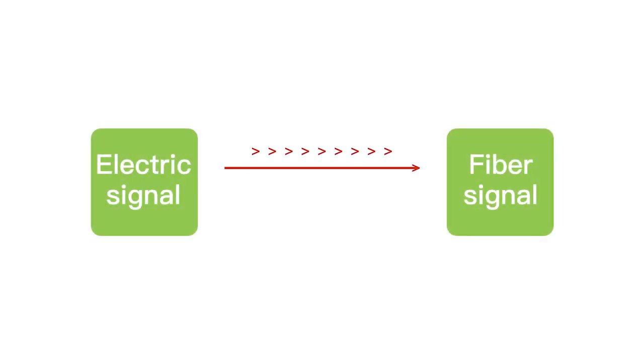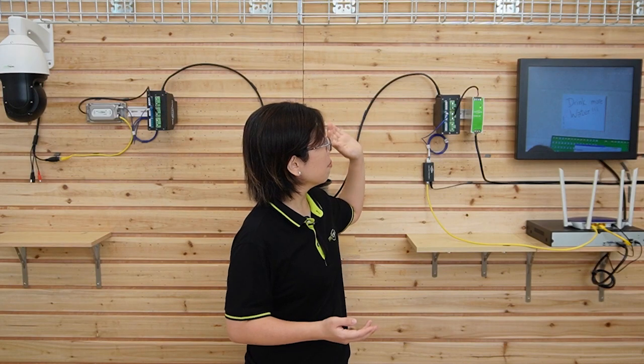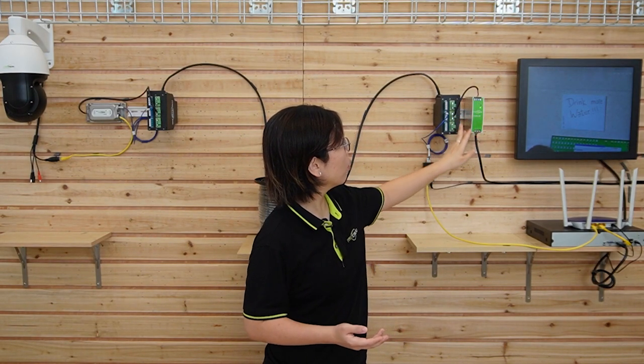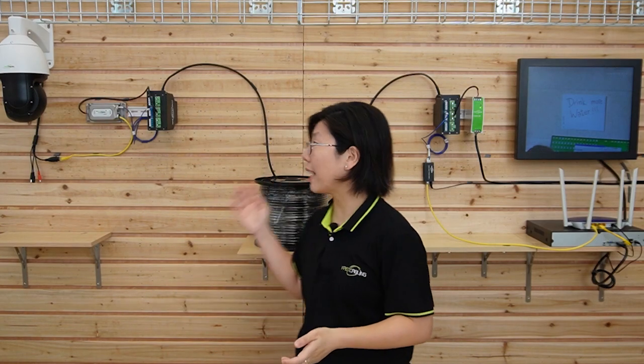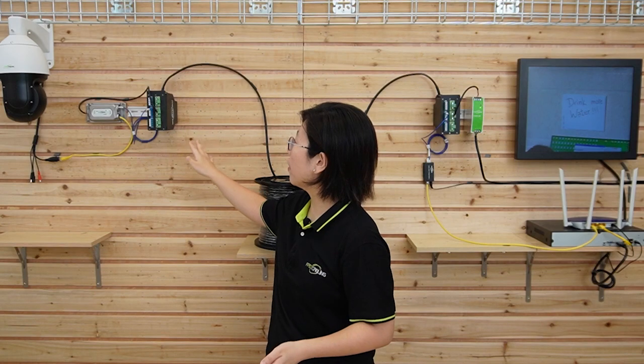A media converter can convert electrical signals into fiber-optic signals in order to travel through the fiber-optic cable. They're already connected to our termination box, which has a power source already connected to a power cord. Coming over to this side, we're injecting the power and data through this composite fiber-optic cable to another termination box, which manages our cable and provides protection.